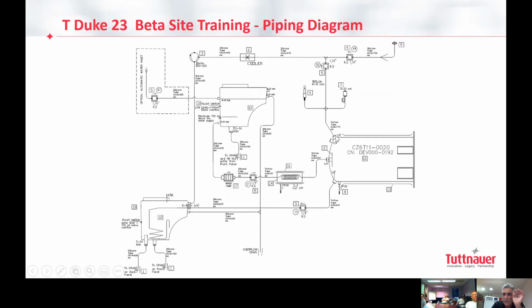So we get a flow, a suction from here all the way via the pump into the waste tank. Clear? Good. And in the meantime, the pressure transducer, 4 to 20 milliamp linear. If you are familiar with the Easy Plus, you are using the same pressure transducer. It's 4 to 20 linear, which is referring to a pressure of 0 to 400 kPa. It's linear.